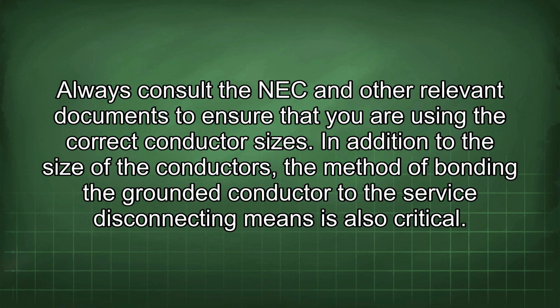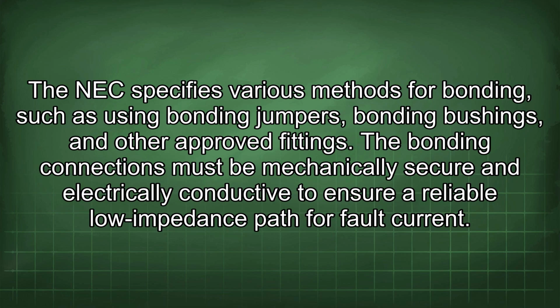In addition to the size of the conductors, the method of bonding the grounded conductor to the service disconnecting means is also critical. The NEC specifies various methods for bonding, such as using bonding jumpers, bonding bushings, and other approved fittings. The bonding connections must be mechanically secure and electrically conductive to ensure a reliable low impedance path for fault current.